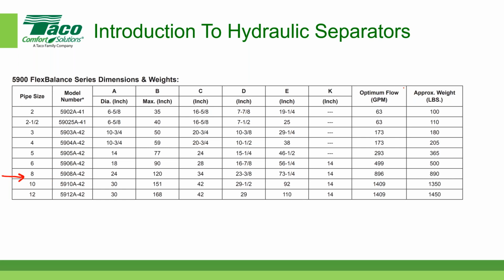Well, if you go all the way here to the right, you'll see where it says optimum flow. And the optimum flow for an 8-inch hydraulic separator is 896 gallons per minute. Well, that's the maximum flow that we want, but our system has 1,200 gallons per minute, 1,200 GPM. So we would not use an 8-inch. We'd have to go to a 10-inch. If you notice, the flow for a 10-inch is 1,409 gallons per minute, and that's greater than the 1,200. So the actual size that you would need would be a 10-inch instead of an 8-inch.